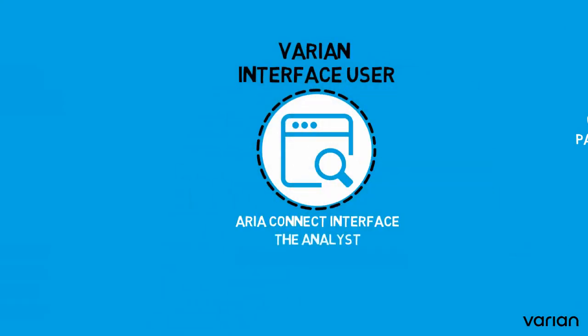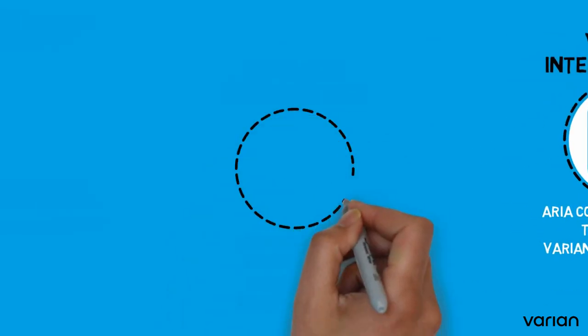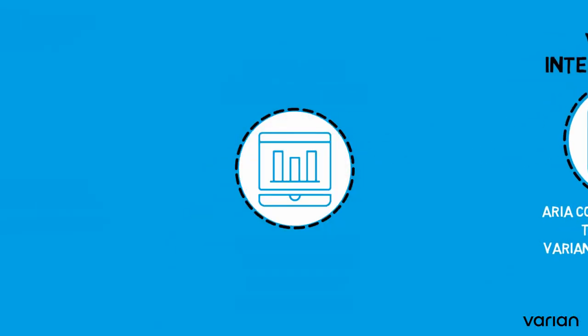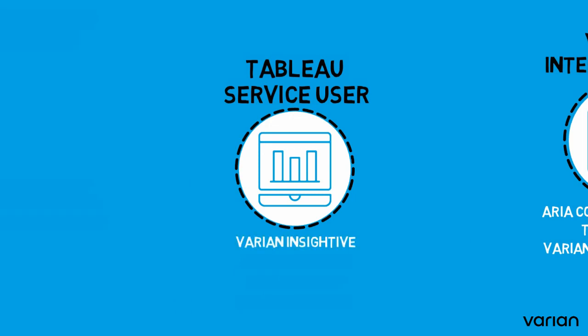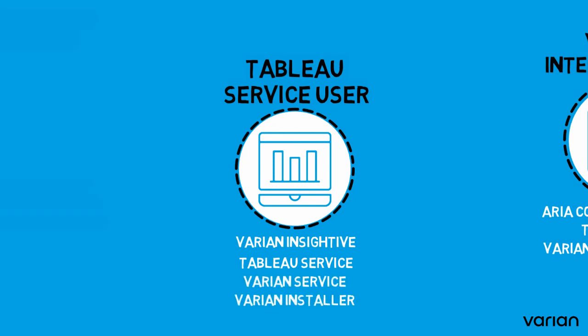The Varian interface user is solely used for the ARIA Connect interface. The analyst will use the Varian interface user to connect and configure the system. The Varian interface engine is an interface that will run the services for the Varian interfaces. The Varian Insightive is a Tableau service user and is not assigned to a group. It will run the Tableau service so that Varian can connect into the system and configure it. Only the Varian service and the Varian installer will have rights to do everything.